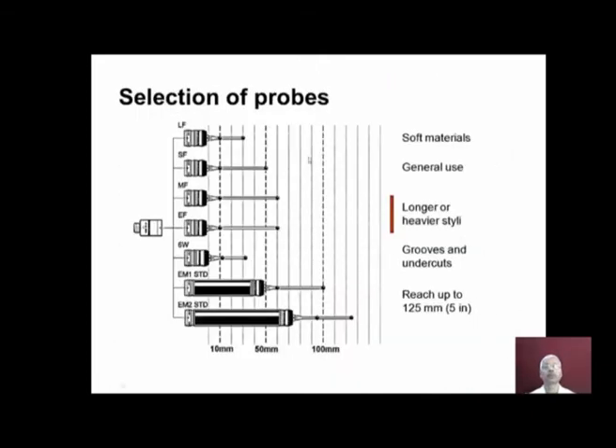Now how do we select the probes? Depending upon the material. If you have a soft material, then we should select the probes with low measurement force requirement. So for general use, we can select the SF type, and for longer and heavier styli, we should use the probes with medium force requirement. And similarly for grooves and undercuts, depending upon the type of the inspection, we should select the probes of appropriate length with appropriate force requirement.